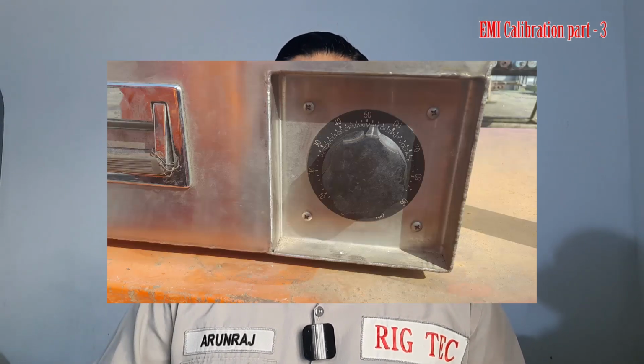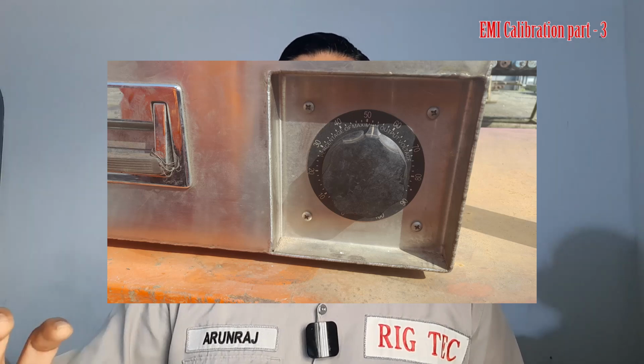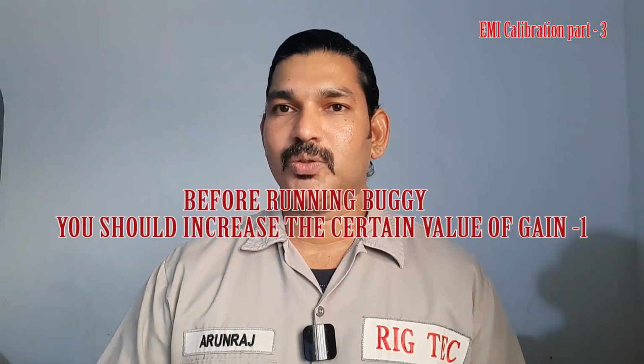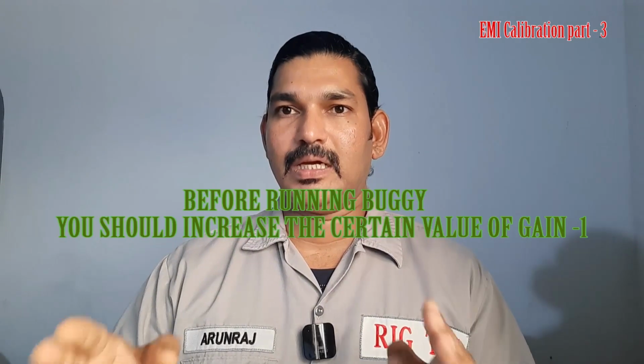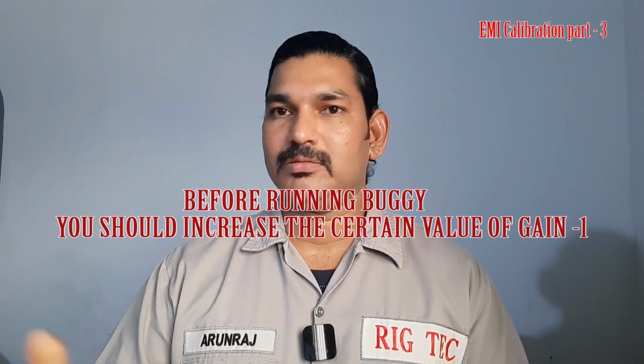We can separate it from the noise. 15 mm is, I think, better, and give the appropriate mag current. You can increase or decrease the mag current through the variac. Variac means a magnetic control. There is a control on the right side of the console. If you rotate it forward, the mag current increases. If you rotate it in reverse, the mag current will decrease. So give the appropriate mag current, 2.5 or 3.5 something.